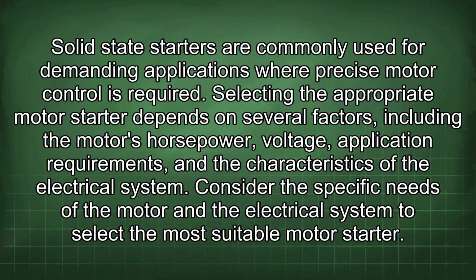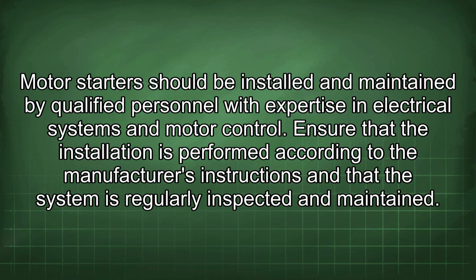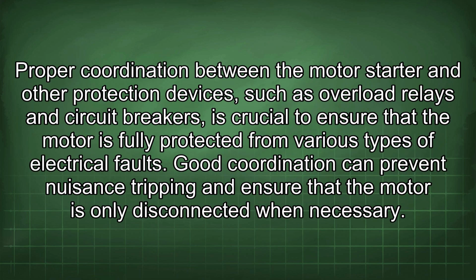Selecting the appropriate motor starter depends on several factors, including the motor's horsepower, voltage, application requirements, and the characteristics of the electrical system. Consider the specific needs of the motor and the electrical system to select the most suitable motor starter. Motor starters should be installed and maintained by qualified personnel with expertise in electrical systems and motor control. Ensure that the installation is performed according to the manufacturer's instructions and that the system is regularly inspected and maintained. Proper coordination between the motor starter and other protection devices, such as overload relays and circuit breakers, is crucial to ensure that the motor is fully protected from various types of electrical faults. Good coordination can prevent nuisance tripping and ensure that the motor is only disconnected when necessary.